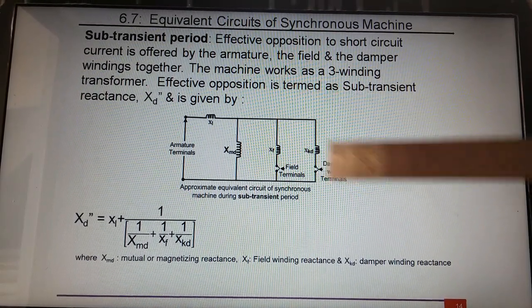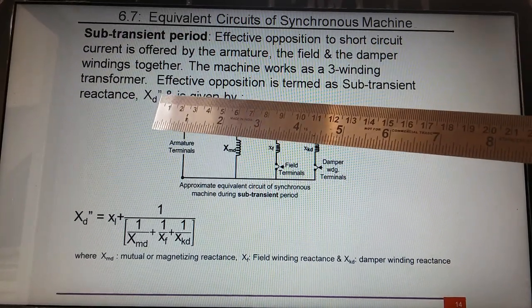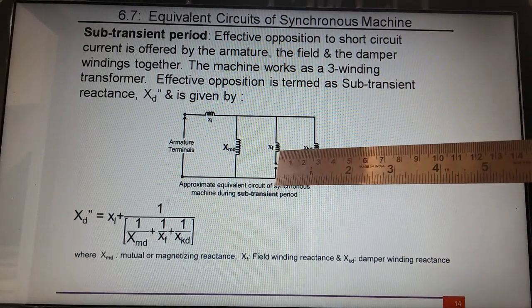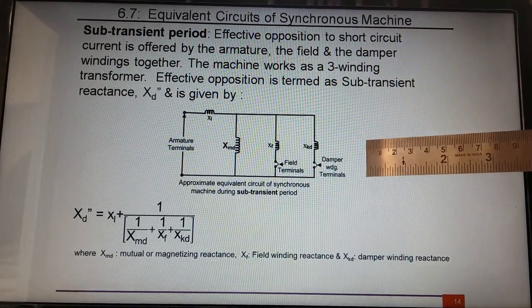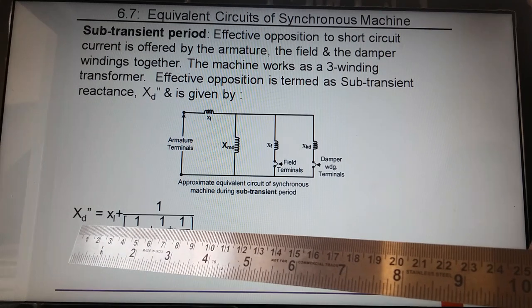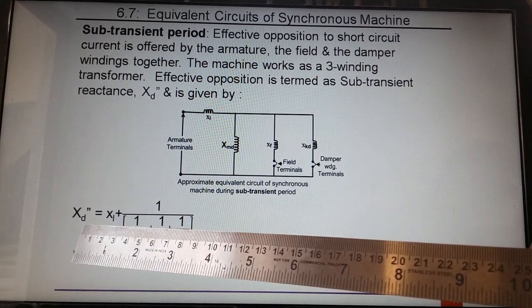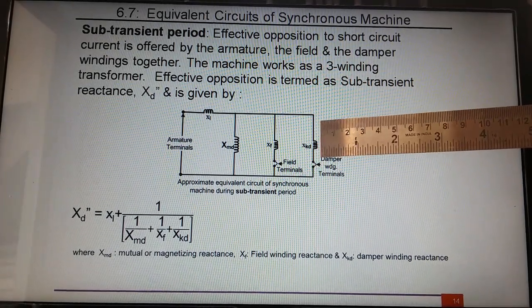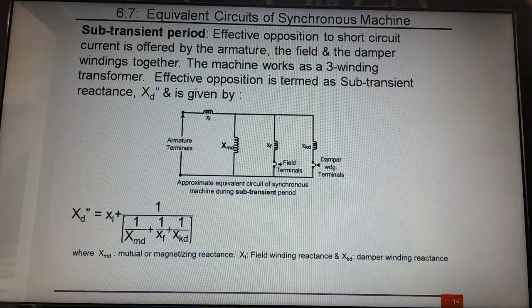The first period is termed the sub-transient period, denoted by double prime. The net reactance offered during this period accounts for leakage reactance, mutual reactance, field reactance, and damper winding reactance in parallel. The sub-transient reactance XD'' — the d-axis reactance offered during the sub-transient period — is equal to XL plus the parallel combination of all three reactances: mutual reactance, field reactance, and damper winding reactance.